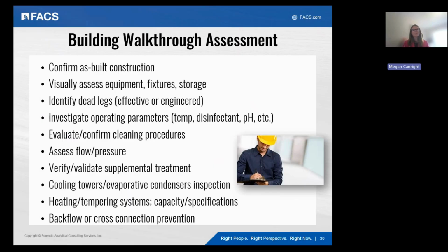If you're aware of cleaning or disinfection procedures, for example for cooling towers, you can evaluate and confirm that on site by physically inspecting the cooling tower, looking at the treatment equipment, and trying to find areas of low flow or pressure issues. If there's supplemental treatment involved, you can verify and validate what kind of treatment is being implemented and how it's being managed.